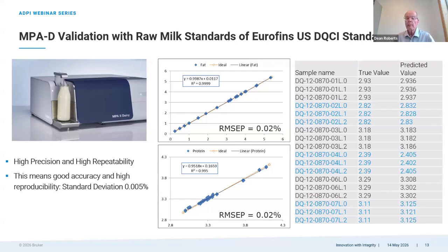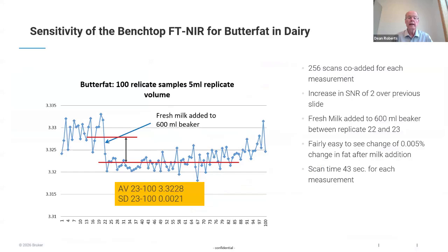So the accuracy of these calibrations is right in line with the repeatability and reproducibility of the standard method that is being used for that, which tells us that the accuracy is about as good as it can really get in terms of comparison to the reference methods. Next slide, Andy. Thank you.